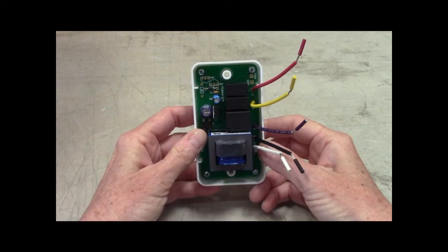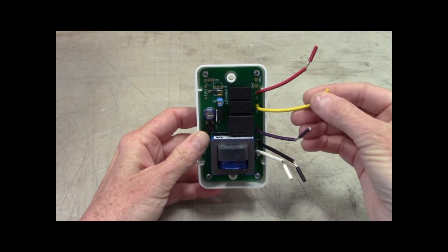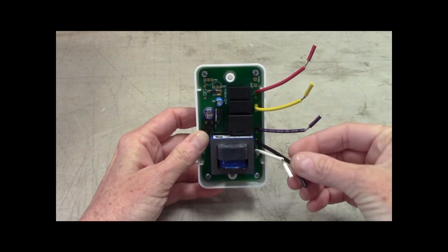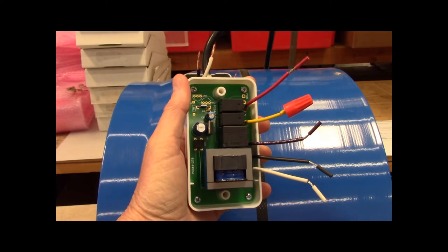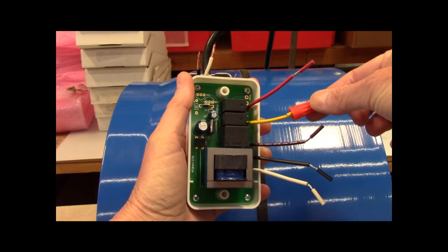The FC3J has 5 wires. Red is the low-speed wire, yellow is the medium-speed wire, purple is the high-speed wire, black is the 120VAC power wire, and white is the neutral wire. I'm wiring the FC3J to a 2-speed fan, so I've already capped the yellow medium-speed wire.